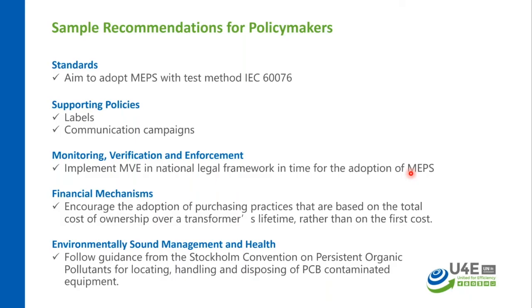The policy guidebook also provides recommendations on product standards, which are generally in line with IEC 60076. It also covers recommendations for countries adopting the 60 Hz standard and the 50 Hz standard as per IEC. 60 Hz standards are generally followed in North America, the Americas, and smaller markets like the Philippines in Asia. The guidebook also provides supporting policies related to labels. Labels are quite a useful tool for transformers purchased largely for buildings, where you have a larger commercial and industrial transformer customer market. That is where labels as a supporting policy will be helpful.